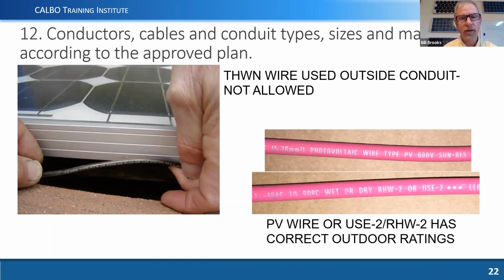Okay, conductors, cables, conduit, types, sizes, and markings according to approved plans. Here we have an example of somebody that wired just standard building wire that's supposed to be in raceways up on a rooftop. That's not going to be very good, especially with a comp shingle roof. So photovoltaic wire, PV wire, may have other ratings on it like RHW or USE2, sunlight resistant, but PV wire and RHW and USE2 are the correct outdoor ratings. This one happens to have all of those ratings on it, for any cable that's not in a raceway.